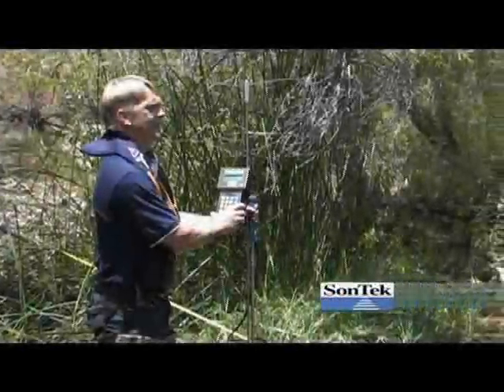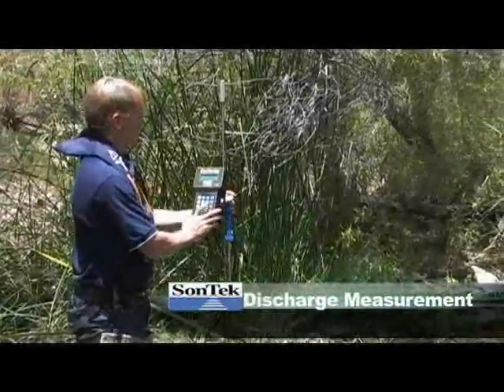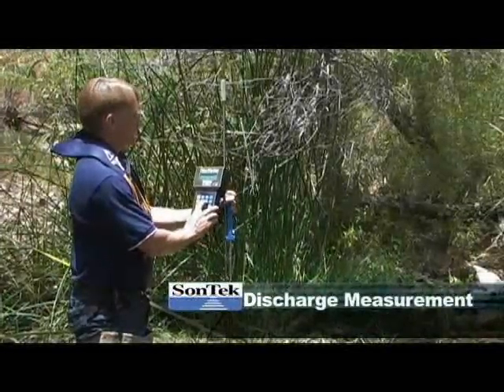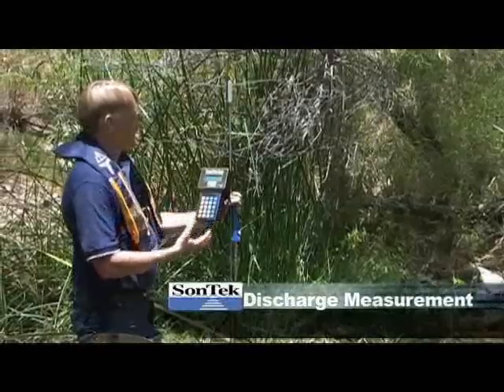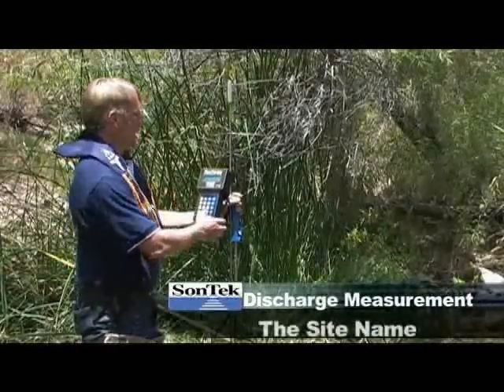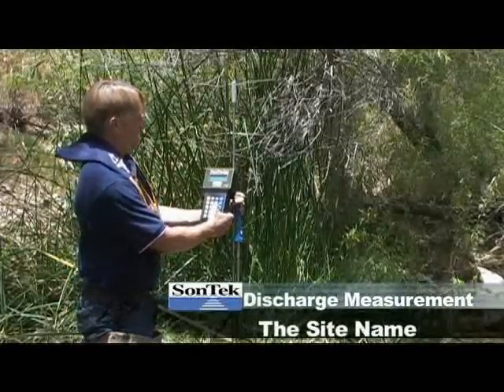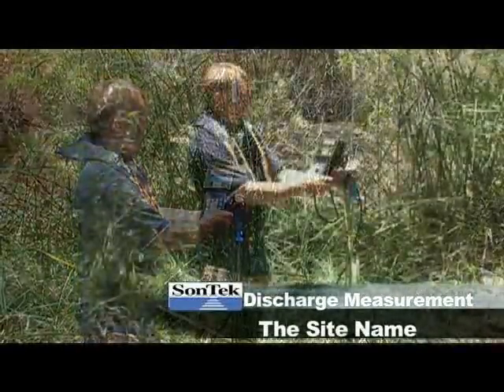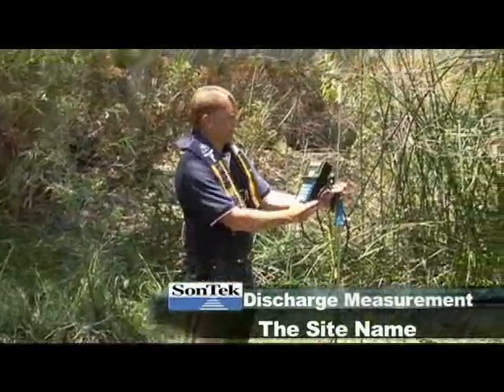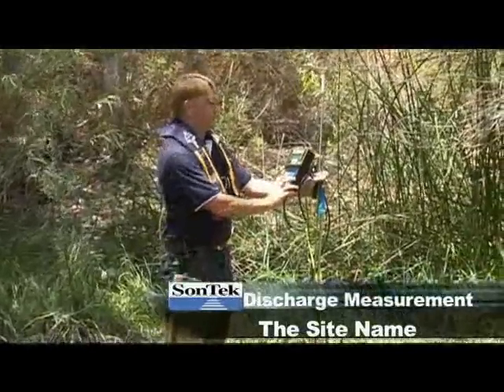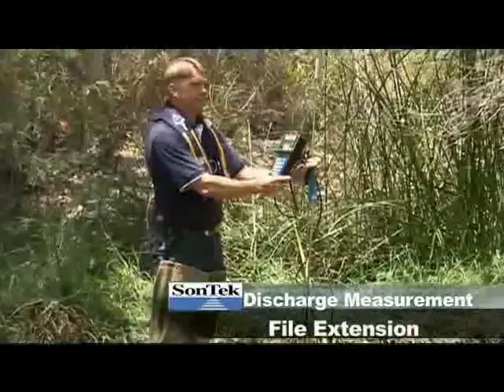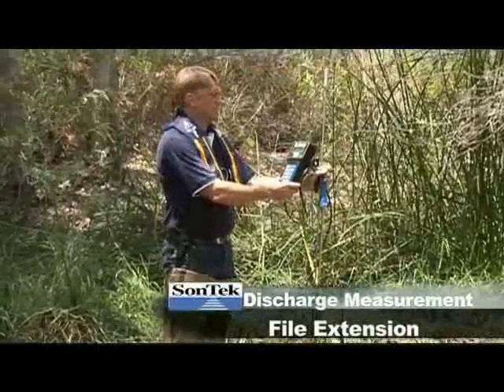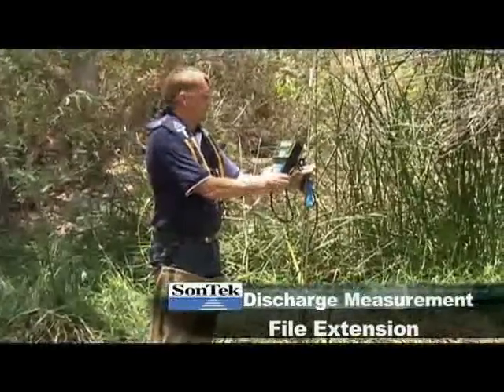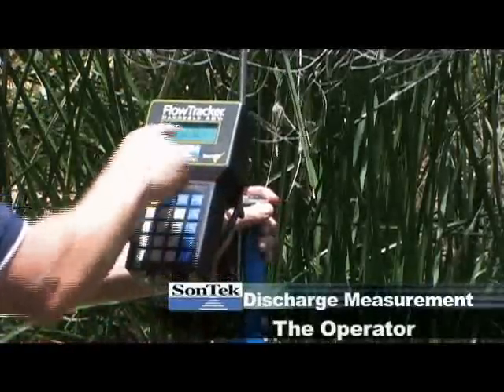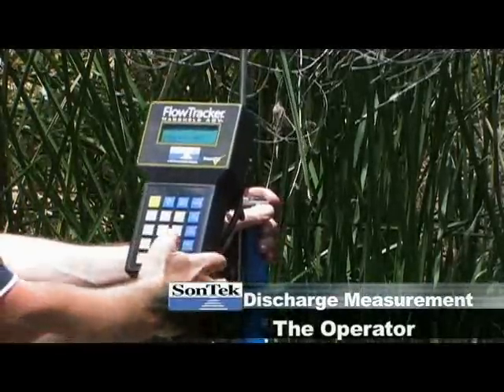Now we're actually ready to make a data run or start our discharge measurement. I'm going to press number 3. The first thing that comes up is it's going to ask me for the name of the site. So I'm going to press 1, and I can put in up to 8 alphanumeric characters. And number 2 is the file extension. Typically I use that as the measurement number, so in this case we'll call it 001. The operator, JVS, that's me, that's the initials.